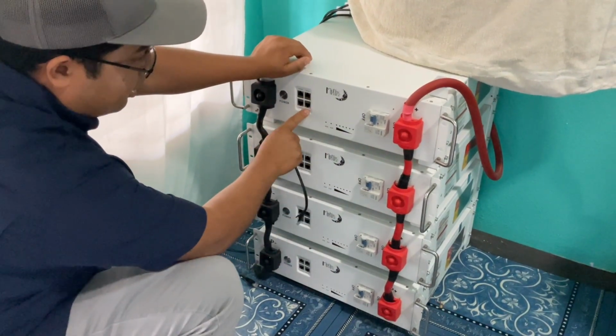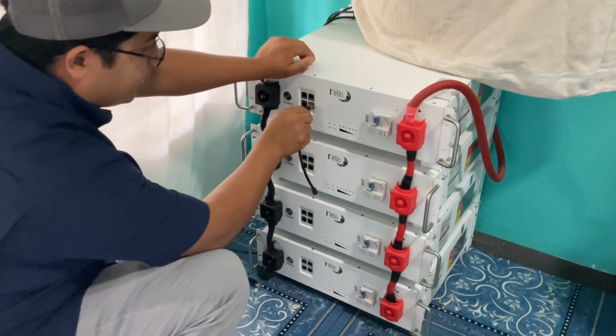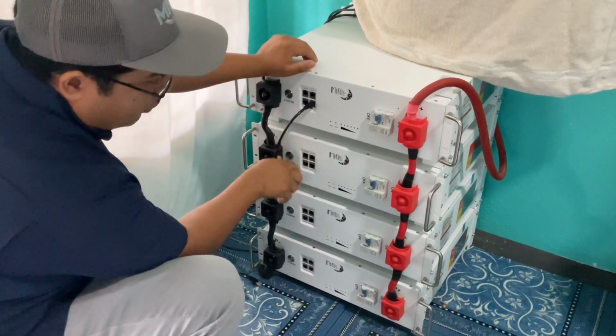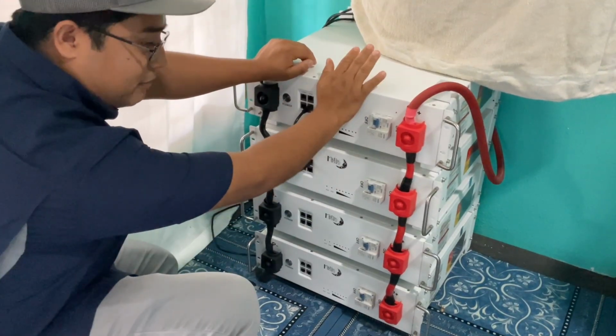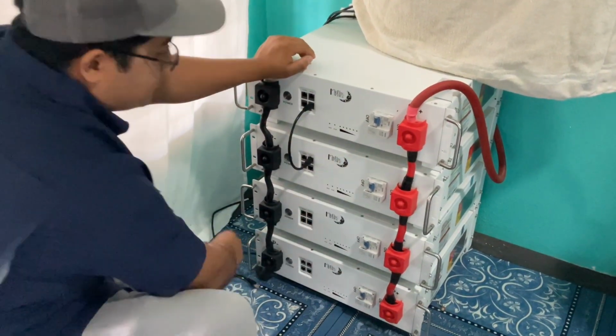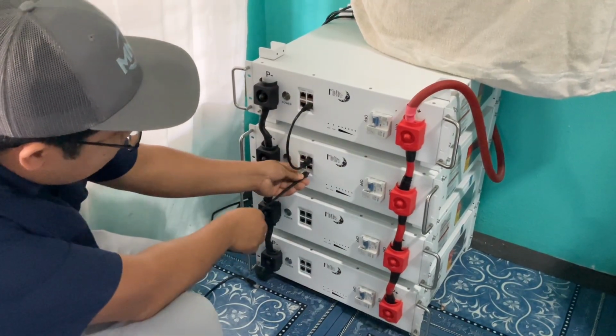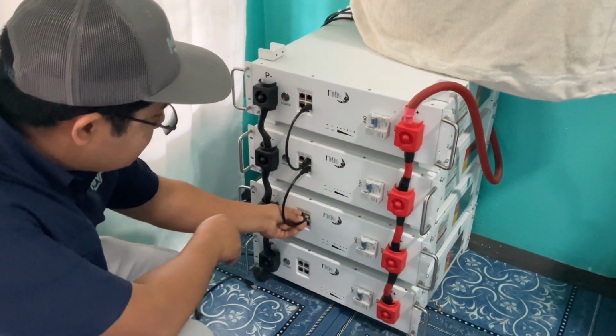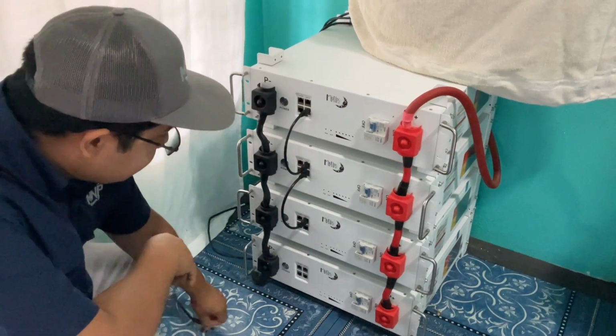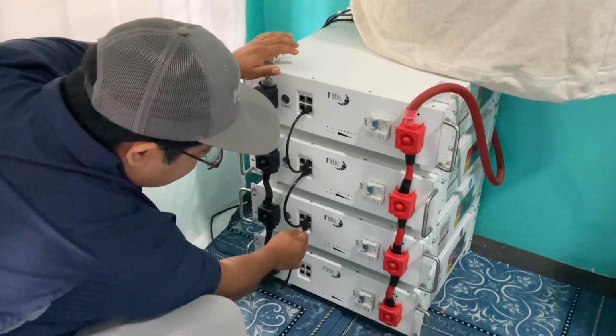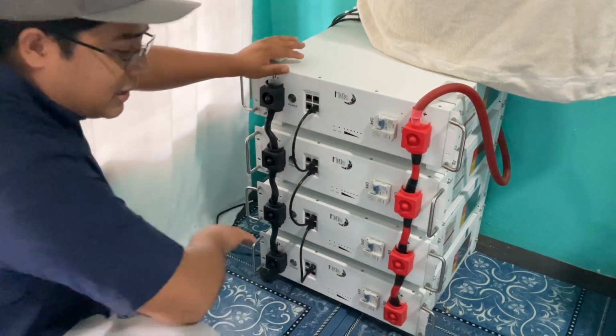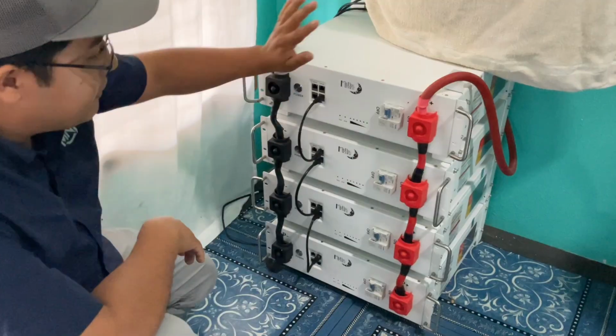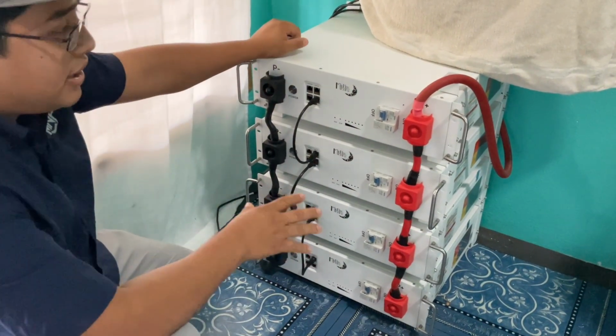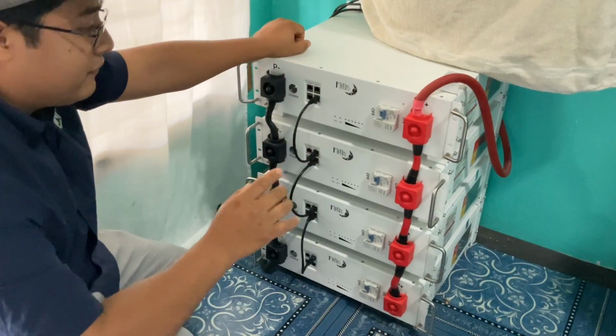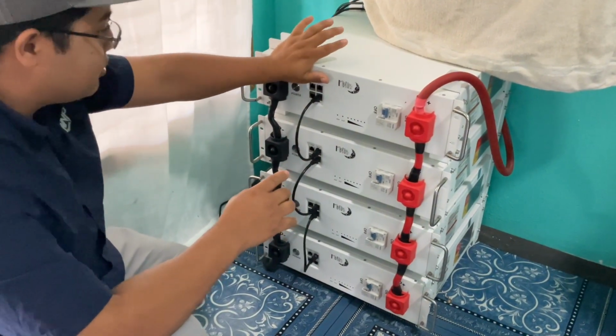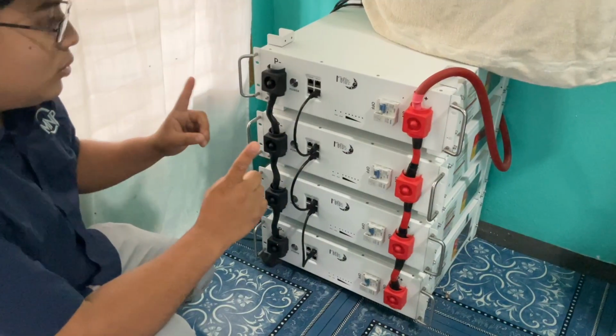We go from the top battery's link out port into the link in port on the second battery. This becomes the master, and the second becomes a slave. From the slave battery, link out to link in on the third battery, the second slave. From that one, link out to link in on the last battery, the third slave. So you have a master and three slave batteries, creating one battery pack. The inverter reads the master, and the master links to the others, so this basically creates one large battery.